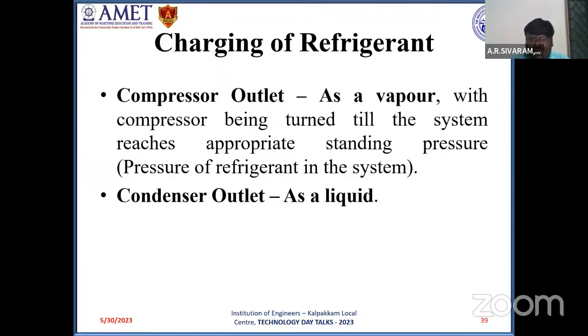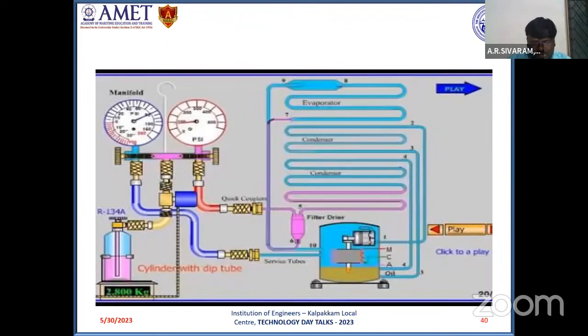But in modern industrial refrigeration systems, as well as in marine refrigeration systems, refrigerants are charged as a liquid at the condenser outlet. There are suitable cylinders which store refrigerant as a liquid, and suitable hoses which transfer refrigerant as a liquid from the cylinder to the system. Here, charging is done at the compressor inlet. R134A is charged at the compressor inlet, with the compressor turned on till the system reaches the required pressure.